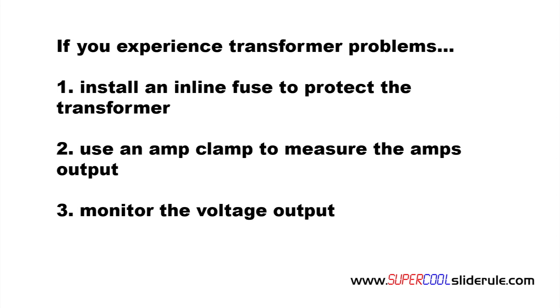Normally a 24 volt transformer actually puts out about 26 volts. If you measure this once the load is added and you notice it fall below about 22 volts, you probably have too small of a VA transformer. In this instance you would replace the 40 with either a 50 or a 75 VA transformer.